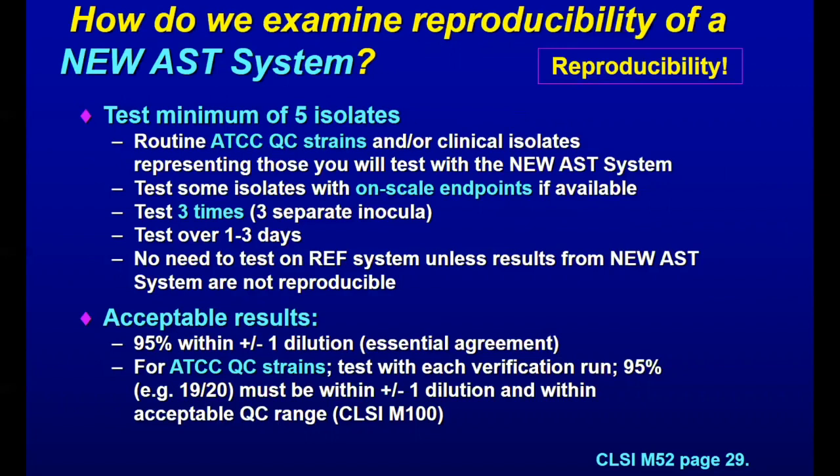Test some isolates with on-scale endpoints if these are available. And why I say if available: with some of the new very active drugs, it's very hard to find some resistant isolates. Test these 3 times using 3 separate inocula. You could test all on one day or on individual days.